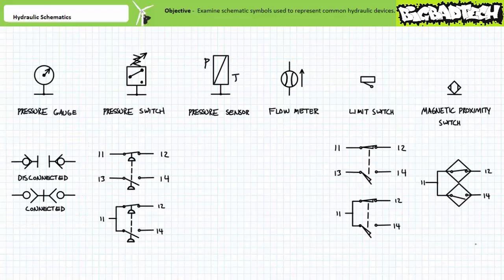Pressure switches and sensors also monitor pressure for automatic systems. The schematic symbol for a pressure switch is a box with an input port and a single-pole double-throw transfer switch symbol inside the box. The spring and slanted arrow indicate that the set value is adjustable. Sometimes span, the difference between the set and reset values, is independently adjustable. Given pressure switches are point of interaction between the hydraulic and electrical aspects of an electrically controlled hydraulic system, the same pressure switch will also have an associated electrical schematic symbol.